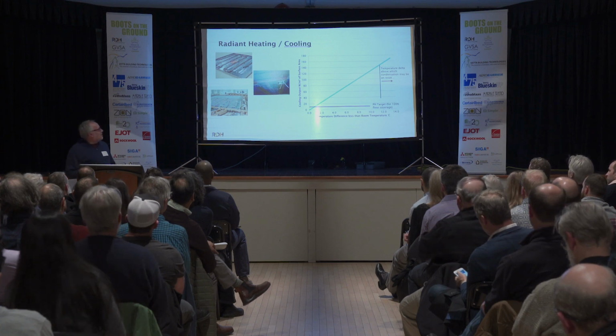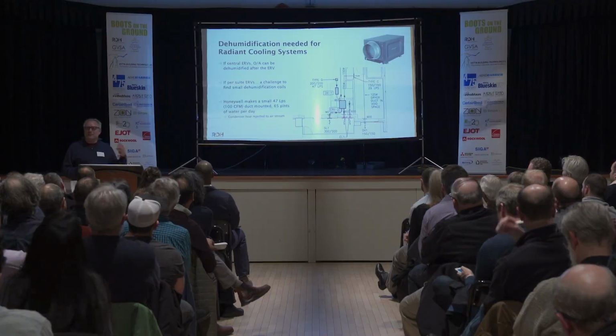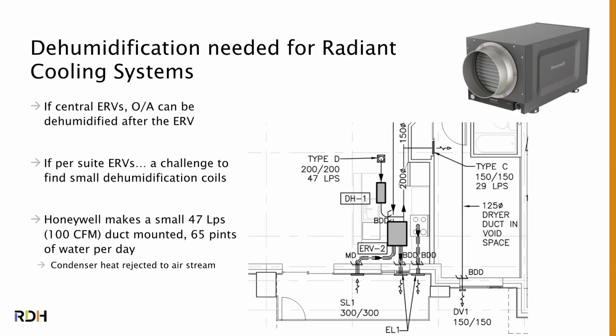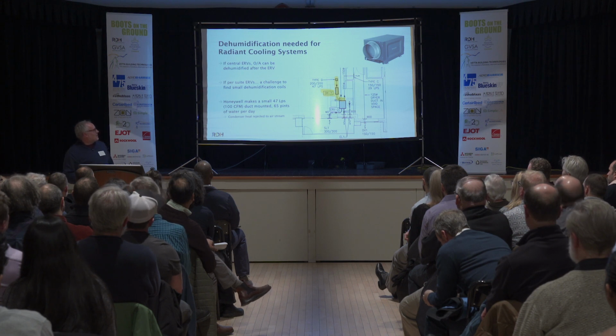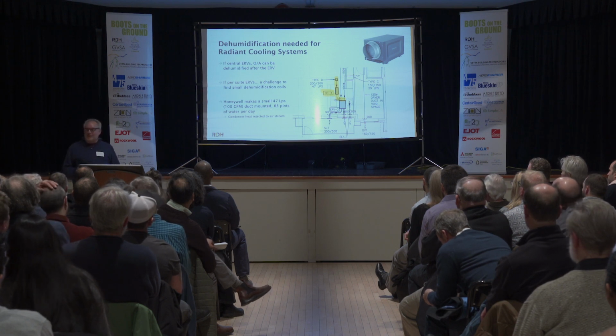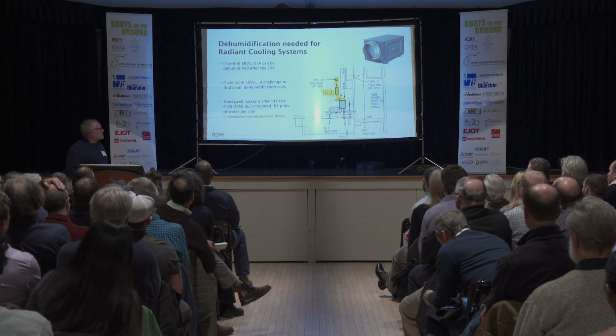The challenge, of course, with radiant cooling is you need to dehumidify. Now, if you're doing passive house with a central HRV or one per floor, you probably have a cooling coil there. You're dealing with the humidity there. This particular project was doing HRVs per suite, which meant we now had to find a 100 CFM dehumidifier coil, which is really, really hard to find. But it turns out Honeywell does make one. Unfortunately, this is the old-fashioned dehumidifier where the heat literally goes back into the space. It's capable of removing 65 pints of water a day, which is 8 times more than we need. But it's the smallest one we can find on the market.